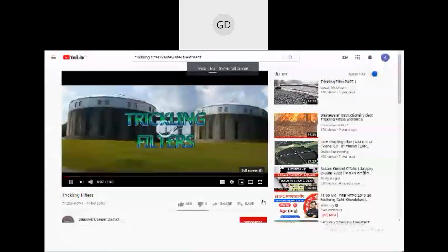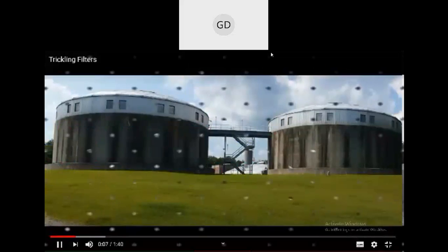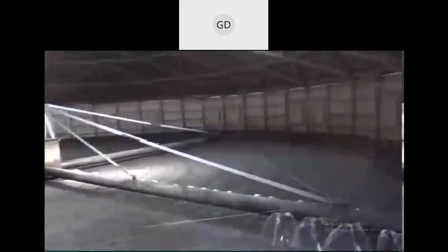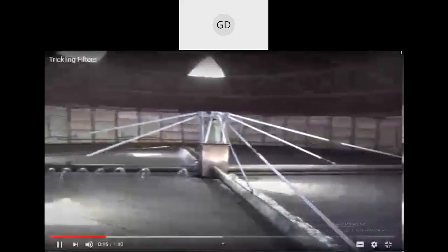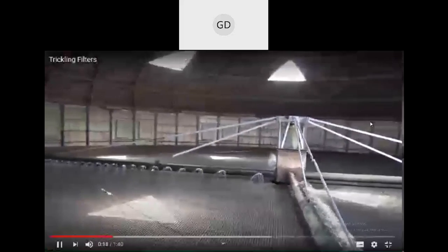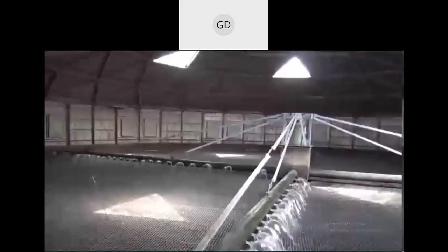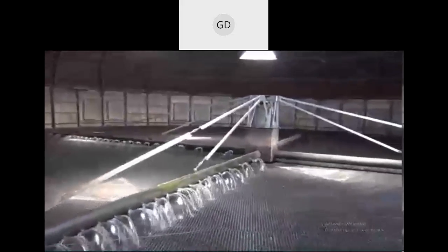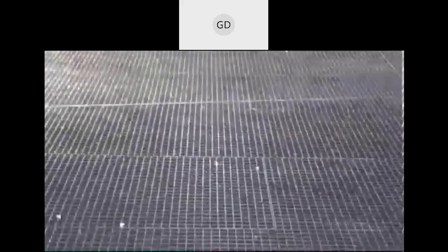Pump to the trickling filters, the mechanical and physical processes of primary treatment are concluded. The next step is biological treatment, which is known as the secondary treatment process. The wastewater that is pumped from the primary effluent wet well to the top of the two trickling filters is spread evenly across the surface of the filters through revolving pipes known as distribution arms. These arms have holes known as ports. The trickling filters are 86 feet in diameter and about 46 feet tall. You can see these structures as you drive along Route 1 between Cook's Corner and Main Street.